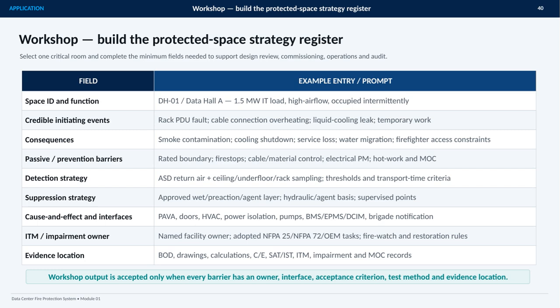Next, record the barriers that prevent or limit the event. These may include rated boundaries, fire stops, material controls, electrical maintenance, hot work controls, and management of change. Define the detection approach, including air sampling locations, thresholds, and transport time criteria. Then capture the suppression basis, supervised points, and the selected wet, preaction, or agent system. The register must also show cause and effect interfaces, including doors, HVAC, power isolation, pumps, building and operational systems, and brigade notification. Finally, identify the ITM owner, impairment and restoration rules, and the location of supporting evidence.